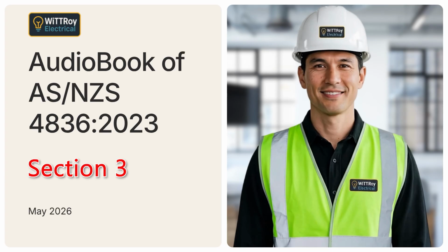The worker must also consider alternative power supplies. These may include UPS systems, standby generators, solar supplies, batteries, emergency supplies, ring main systems, neutral backfeed, separate auxiliary control supplies, multiple control supplies, and ELV control circuits that may backfeed through transformers. ELV means extra low voltage. This is an important point because many modern installations have more than one possible source of supply.